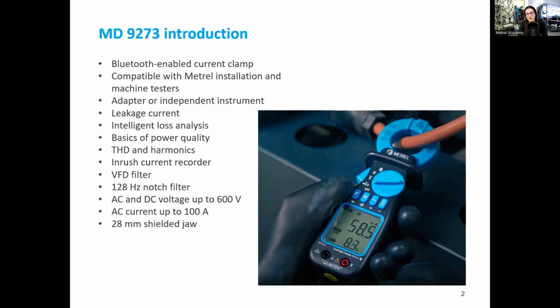Then we have the basics of power quality. The clamp can measure active, reactive, and apparent power. It can measure the power factor and the angle between current and voltage. The harmonics. The clamp can measure both current and voltage harmonics up to the 19th, and it can also measure the total harmonic distortion in both the current and voltage.